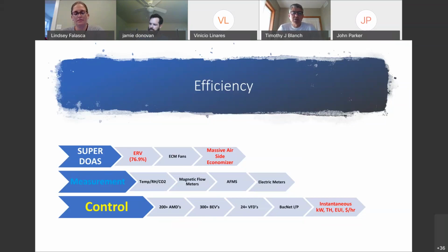I would say from an efficiency design point of view, we were very careful with measurement. All of the temperature sensors are either 2 or 3 function with relative humidity in all of them, so that we control dew point. And a number of them have CO2 sensors built in, and the tenants can read it and see it. You can walk in and see your parts per million of CO2 in a lot of places in the building.